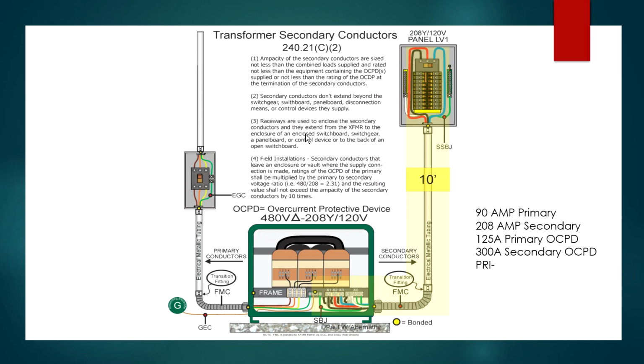It says raceways used to enclose the secondary conductors, and they extend from the transformer to the enclosure of the enclosed switchboard, switchgear, a panel board, or control device, or to the back of an open switchboard. Okay, so in this case right here, they are coming in, and this is all a raceway. All right, this is EMT. This is a tubing, but under dot 2 of its definitions, EMT does state clearly that it's a raceway. And this is FMC, flexible metal conduit. It is a conduit, and it is also, under dot 2 of its definition, indeed a raceway. So this rule is all good, and this satisfies it, and so I could have a setup just like this.